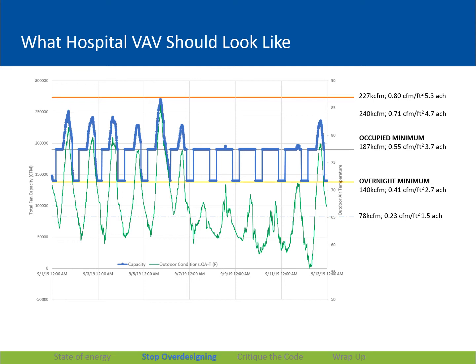You have to do what you have to do. I hear design engineers constantly complaining that, oh, we can't do energy efficiency because the code is limiting. But then we find in the hospitals around the country constant volume systems or really poor VAV systems that do not turn down. And so I said at the top of this presentation that most of the energy that we're wasting is not code related. It's design practice related. This is what I mean.